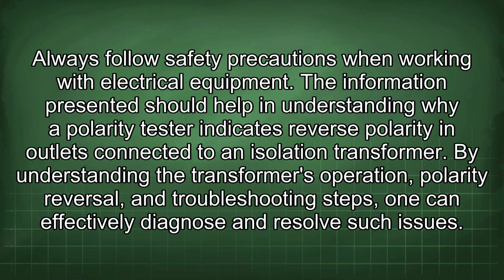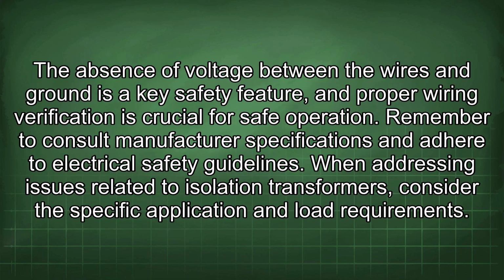The information presented should help in understanding why a polarity tester indicates reverse polarity in outlets connected to an isolation transformer. By understanding the transformer's operation, polarity reversal, and troubleshooting steps, one can effectively diagnose and resolve such issues. The absence of voltage between the wires and ground is a key safety feature, and proper wiring verification is crucial for safe operation. Remember to consult manufacturer specifications and adhere to electrical safety guidelines.